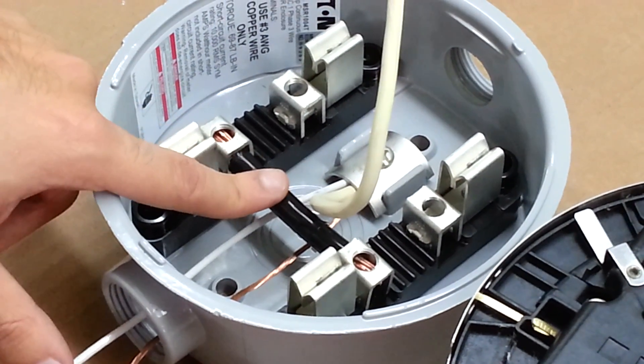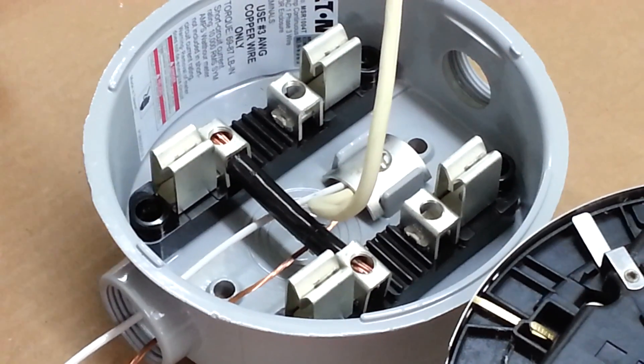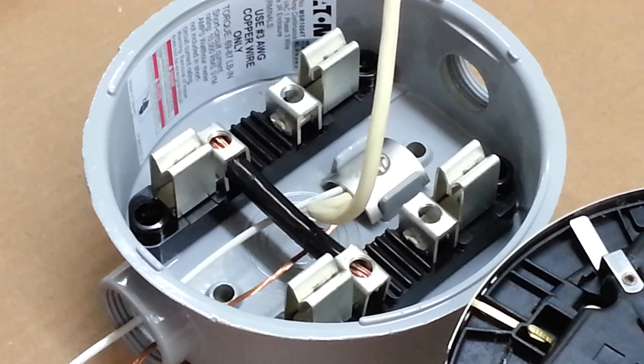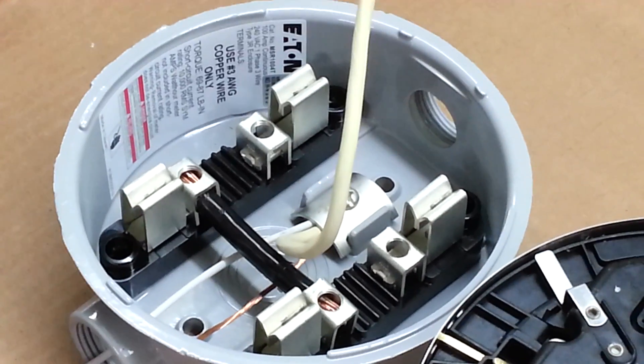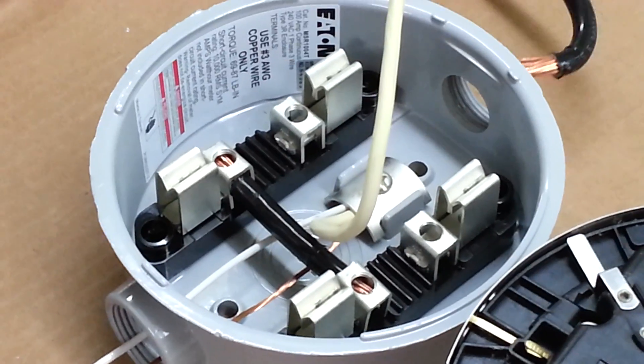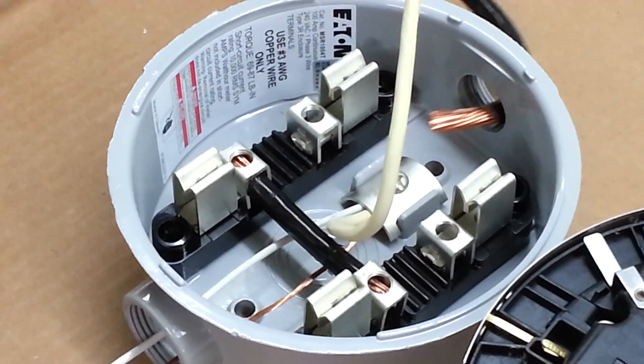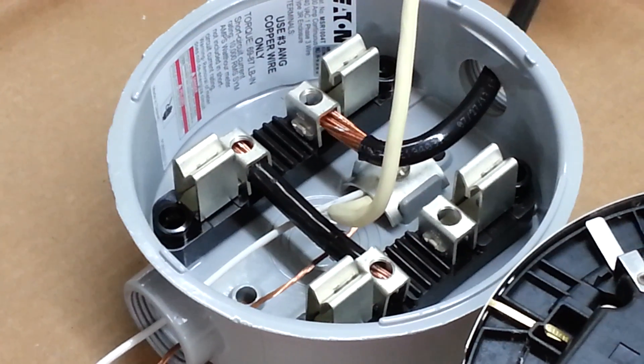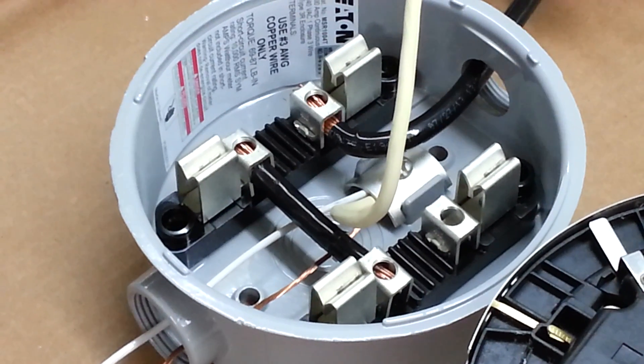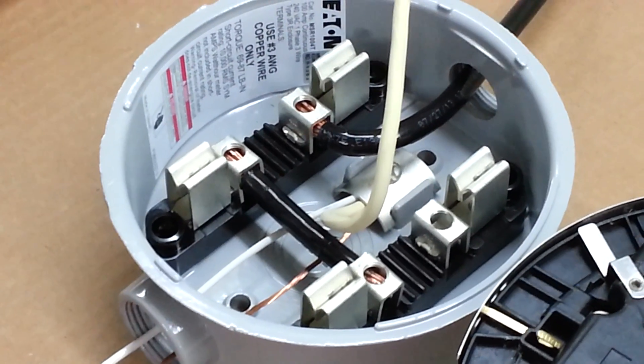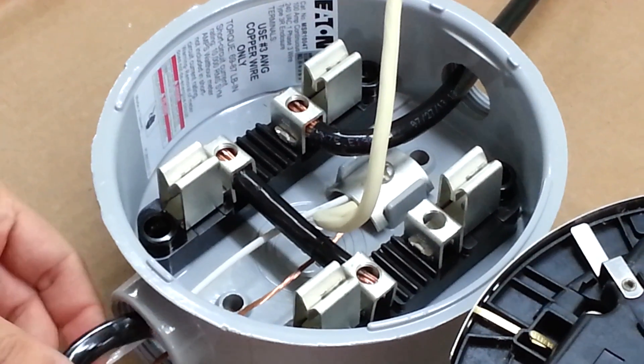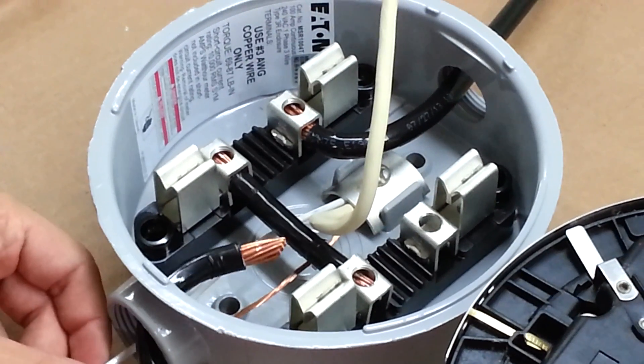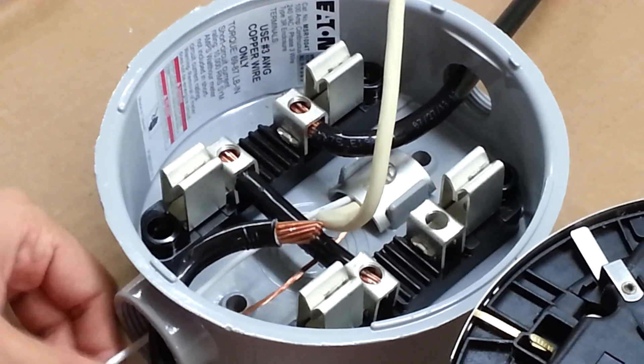This wire can be number 3 gauge. The incoming line from the service will be connected to the upper left lug of the socket, and the outgoing service to the load is connected to the upper right lug.